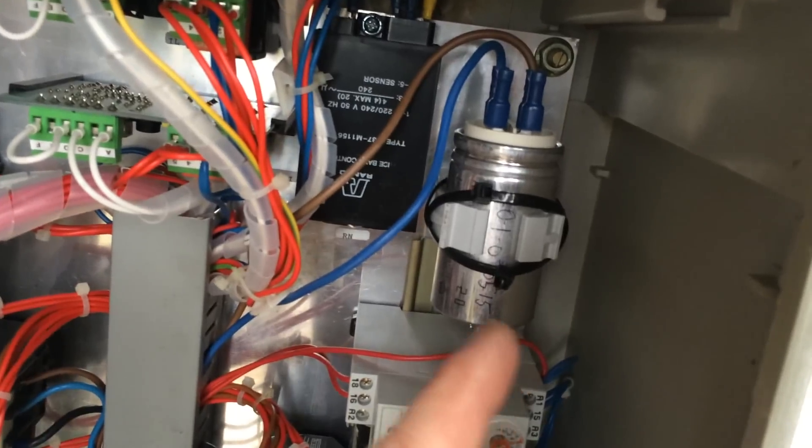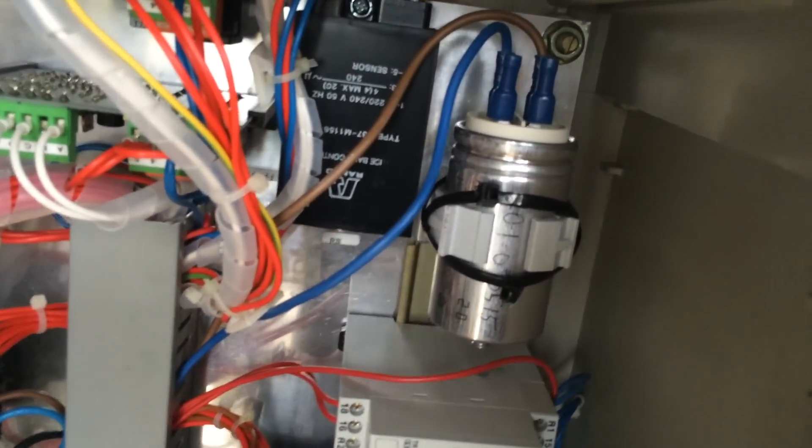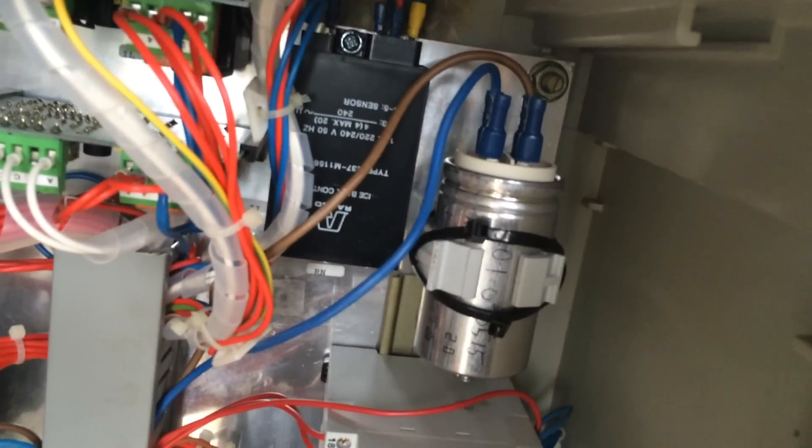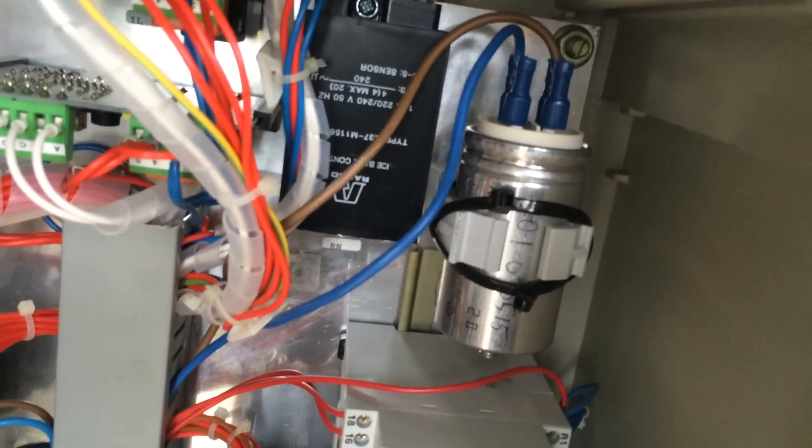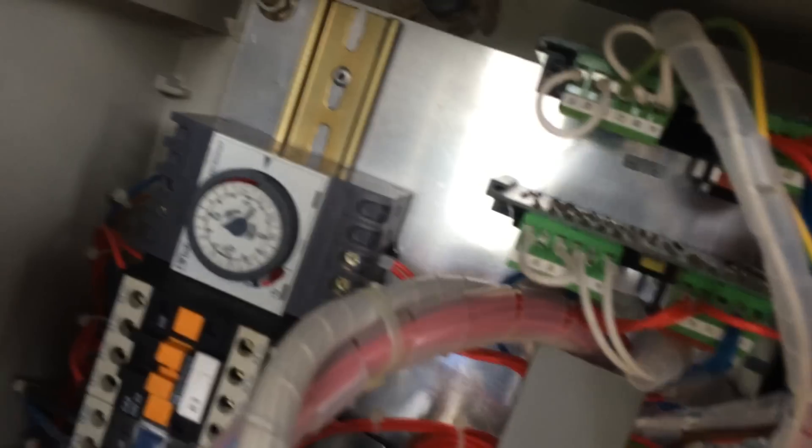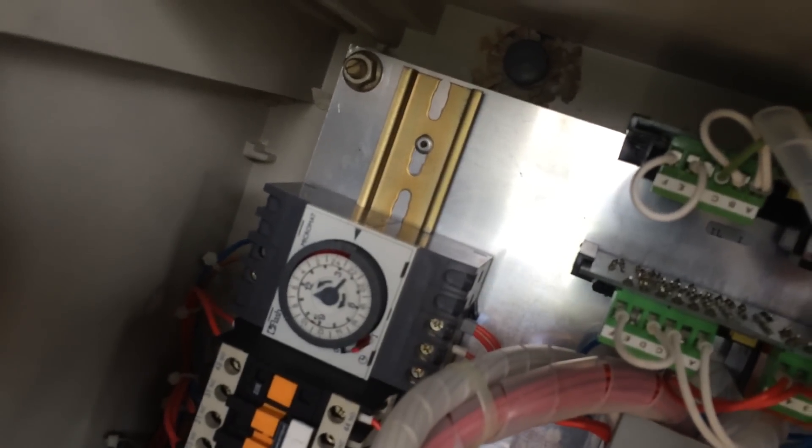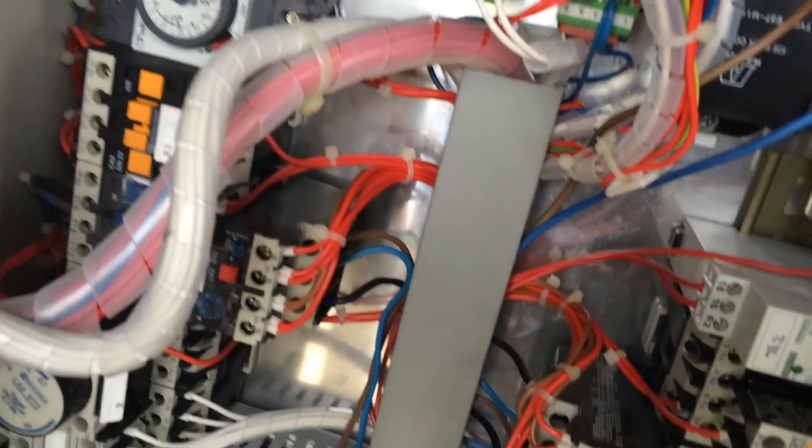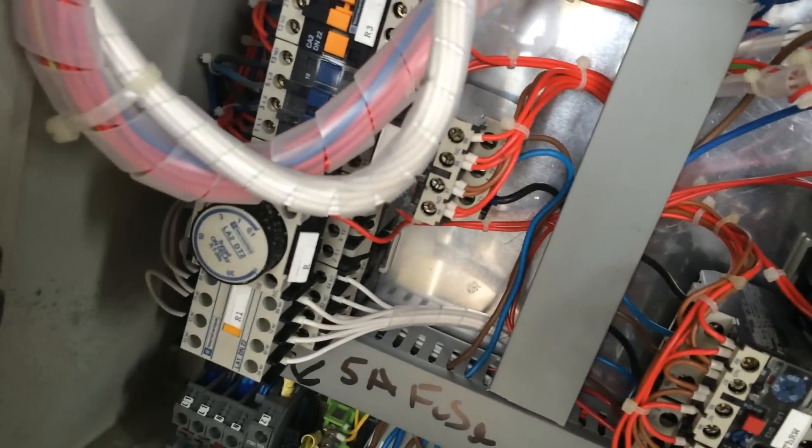Check that capacitor that does the water pump, because that's the other thing that can play up. If the pump doesn't start and pump the ice water around, it won't cool. And we'll check the capacitor on the agitator, because again they can give trouble.